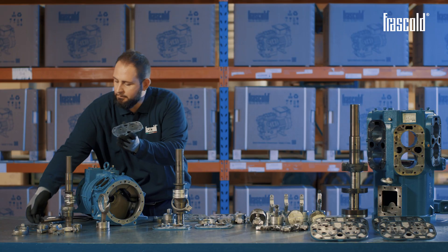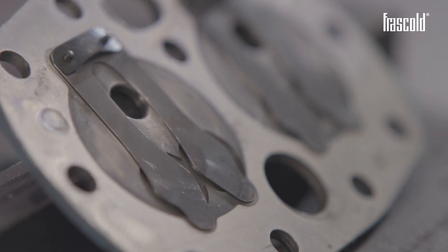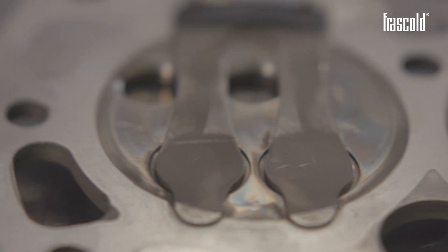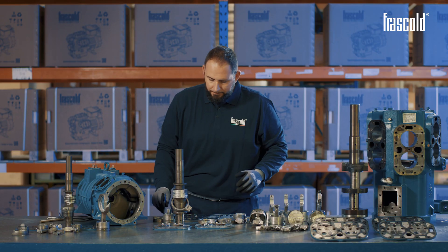We can see the purple color on the suction side of the valve plates. This is due to the massive passage of refrigerant gas from the suction side to the discharge side. The rapid thermal shock weakens the valves causing them to break.